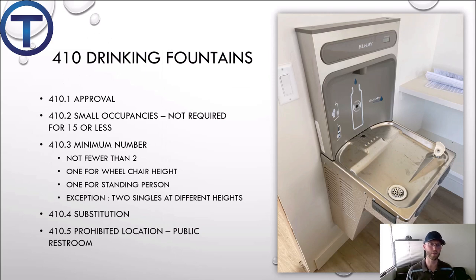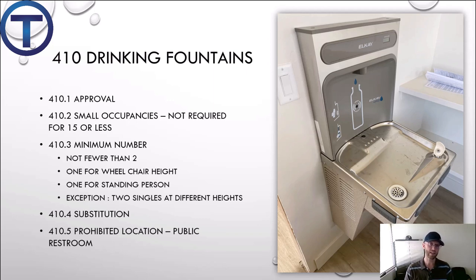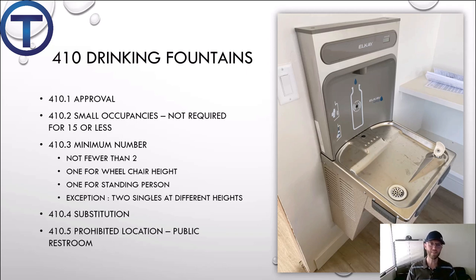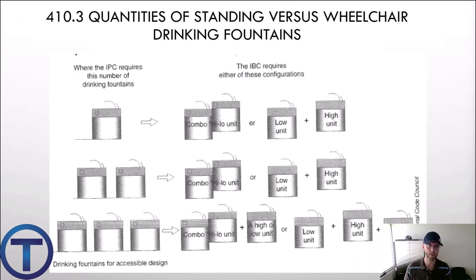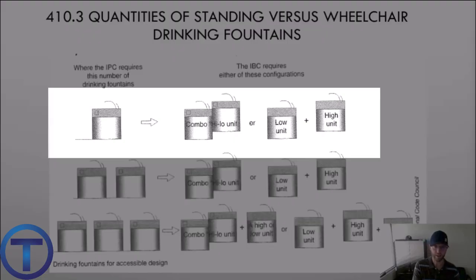410 covers drinking fountains. 410.1 has the approvals and standards that drinking fountains must meet. 410.2 says that if there are fewer than 15 people in an occupancy, a drinking fountain is not required. 410.3 gives the minimum number of drinking fountains when required, and states that you must provide for both wheelchair users and standing users. So if one drinking fountain is required, you need one at each elevation — either a combined high-low unit or two separate units.